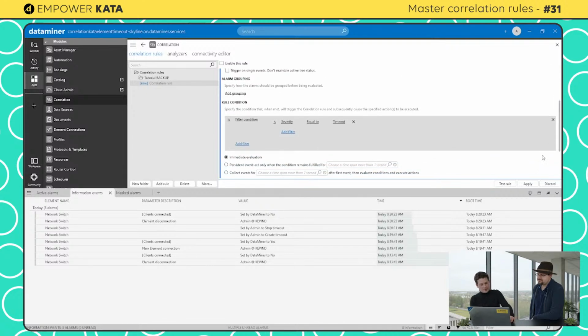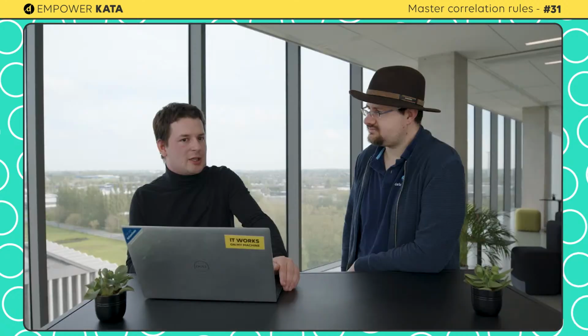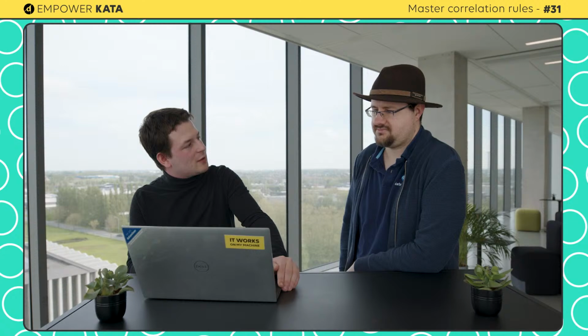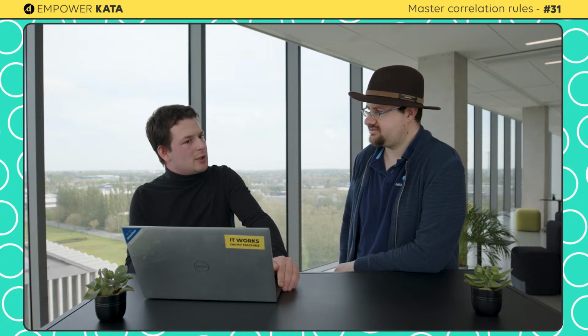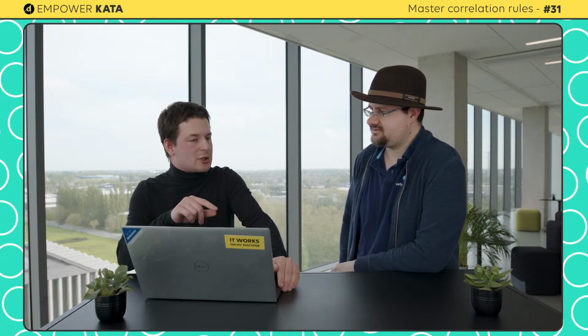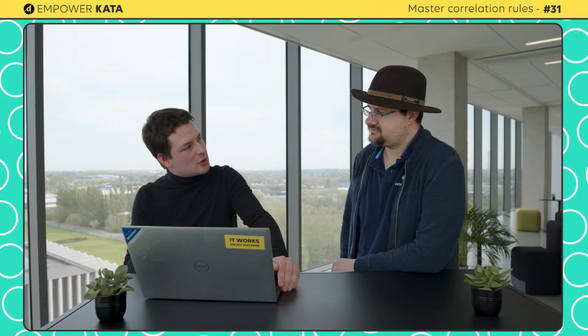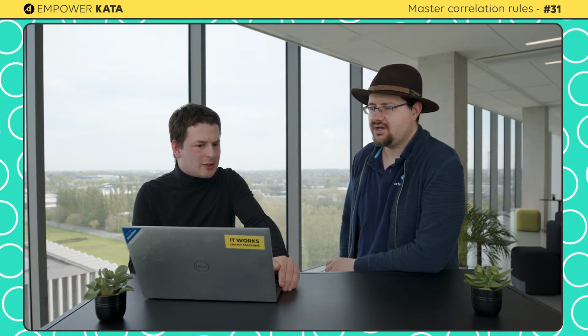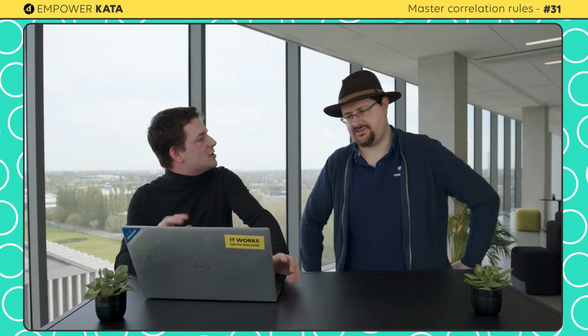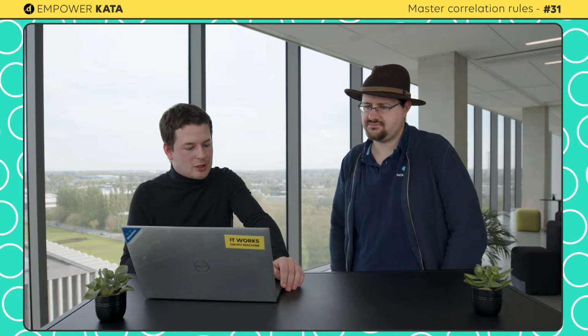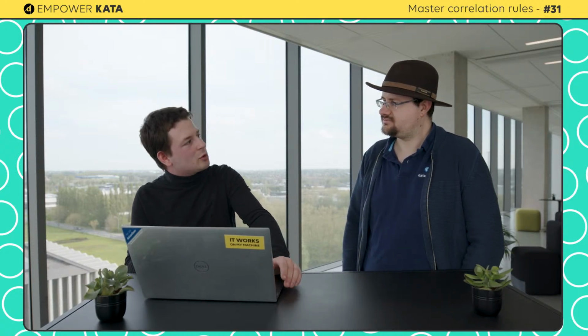So if you apply this and you enable this rule, if a timeout happens, so basically if an element isn't responsive, it will immediately trigger. Yes, but if an element stops responding, the default in DataMiner is 30 seconds before it generates a timeout. For this example, for this tutorial, I changed that to 2 seconds because I don't want to wait that long.